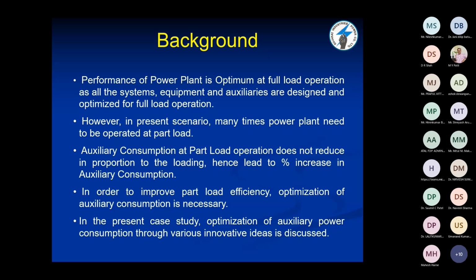So auxiliary consumption at part load operation does not reduce in proportion to the loading. This has led to an increase in the auxiliary consumption. So the percentage of auxiliary consumption increases, because there are so many auxiliaries that we cannot run at part load. They have to be run in full load condition, whereas our main machine is running at part load operation. So there will be a percentage increase in the auxiliary consumption relative to generation. So in order to improve part load efficiency, optimization of auxiliary consumption is very necessary. Okay.